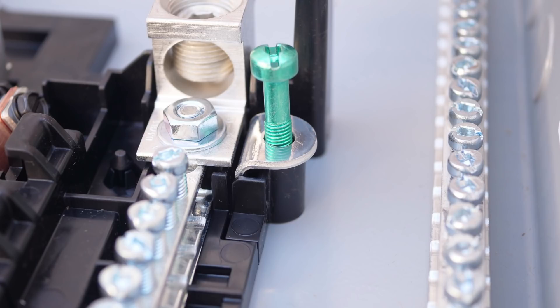And once again, it would be my suggestion to remove this bonding screw from this panel if you're not going to use it to bond the neutrals and the grounds. If you leave it loose, it will not bond your neutrals and your grounds, but it might be inviting to a do-it-yourselfer to tighten that down because you look at it and say, oh, the screw is loose. It needs to be tightened down and that could mess up your grounding and bonding.